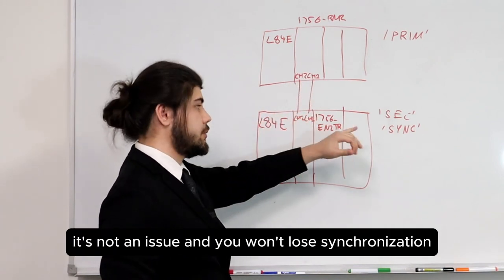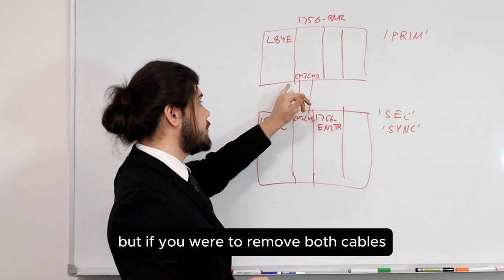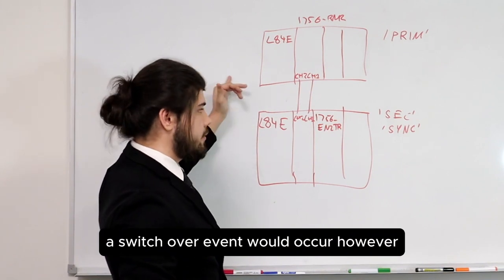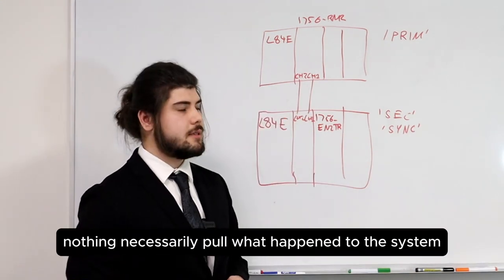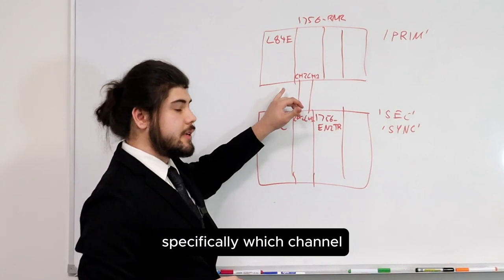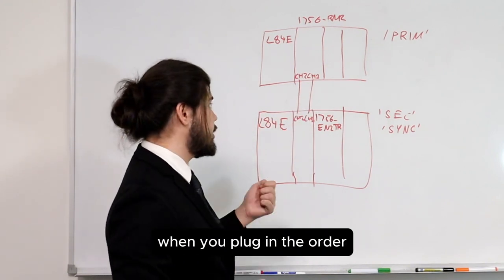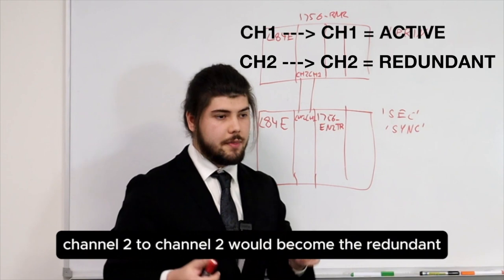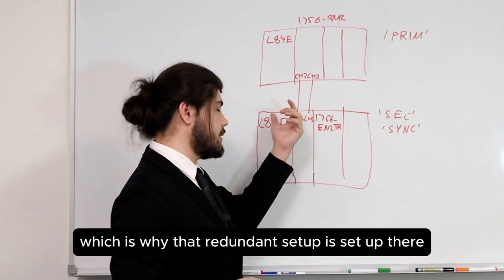If you unplug one fiber optic cable, it's not an issue and you won't lose synchronization, because the other cable will become the active — it performs its own little switchover for the cables without doing it for the PLCs. If you remove both cables, a switchover would not occur because the system identifies the cable as the fault and not the PLC. No switchover event would occur, but the secondary that was synchronized would no longer be able to cross-load and would become disqualified. In software, there is no way to designate which channel or cable is active for cross-loading versus standby — that's entirely based on which order you plug them in. There is no way to remotely switch which channel is active, but the system will automatically handle it if there is a fault in the cable.